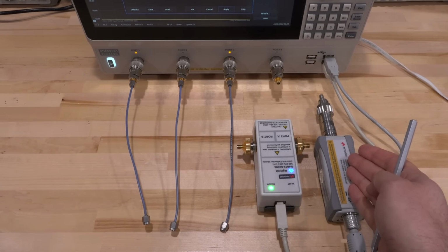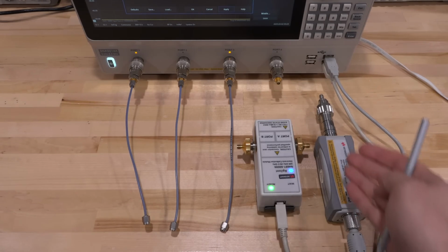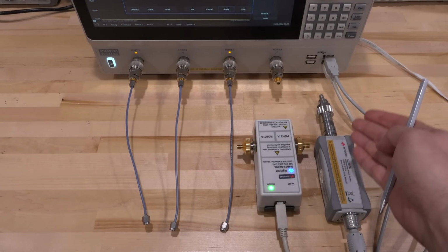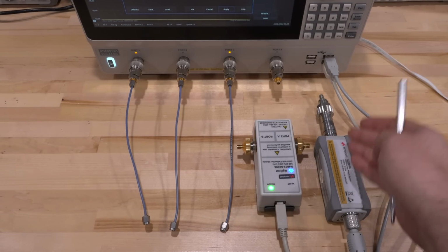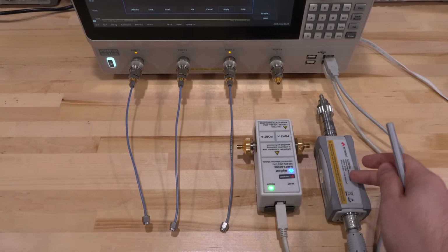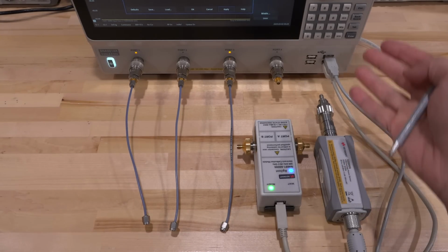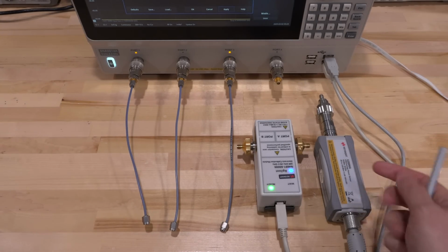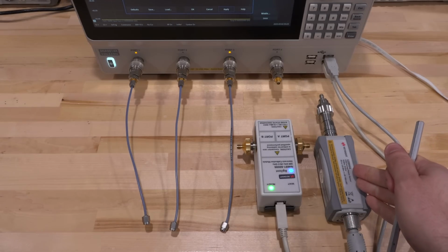The power cal is simply using a power sensor like this one, and it's going to sweep the frequency and measure the power using this, which is very accurate, and it's going to calibrate its own sources to make sure everything is correct. That's really handy. Again, you can see I'm using a Keysight one because the instrument supports this particular one as well, which is super handy. Again, I hope that they always maintain that.